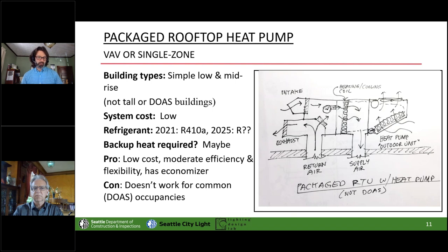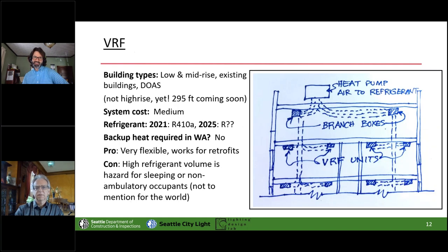And I would strongly encourage you to go read that front section of C403 to know what is requiring DOAS. That's a way to really put your foot in your design. But tried and true. Most of the common building types do require DOAS now, especially in Seattle. But this is a great, cheap way to get it done. They're reasonable efficiency, high flexibility. That economizer is a big energy saver when you don't have DOAS. So good. Okay. This is like a good, better, best situation.